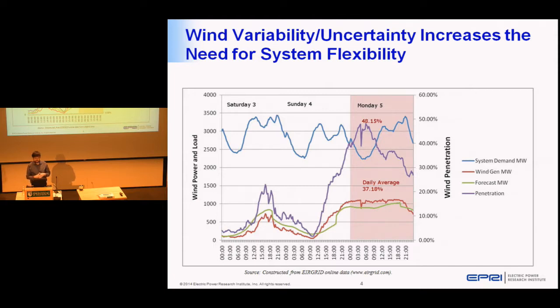Last thing to say about this, the Irish system currently, and it's steadily increasing over time, has limited their penetration level. It's about 55% now. It was 50% at the time. And you can see they're even being a bit conservative there by capping it at 48. But at 48%, or 50% in general, they stop more wind energy coming on. They start feathering blades on the wind energy. That's because from a stability perspective, they're worried that if there was a problem at a generator and it went offline, the frequency on the system would change so significantly that you could end up having a blackout or some significant problems.